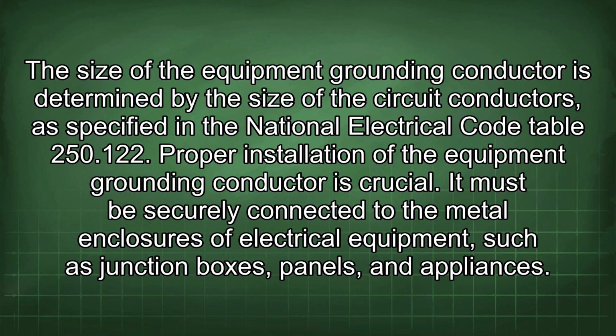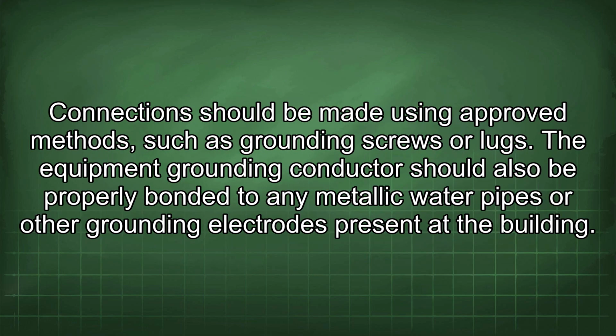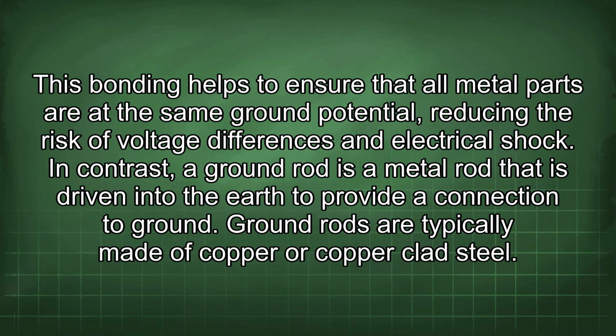It must be securely connected to the metal enclosures of electrical equipment such as junction boxes, panels, and appliances. Connection should be made using approved methods, such as grounding screws or lugs. The equipment grounding conductor should also be properly bonded to any metallic water pipes or other grounding electrodes present at the building. This bonding helps to ensure that all metal parts are at the same ground potential, reducing the risk of voltage differences and electrical shock.